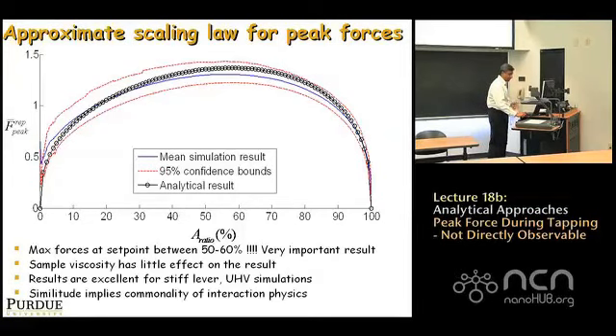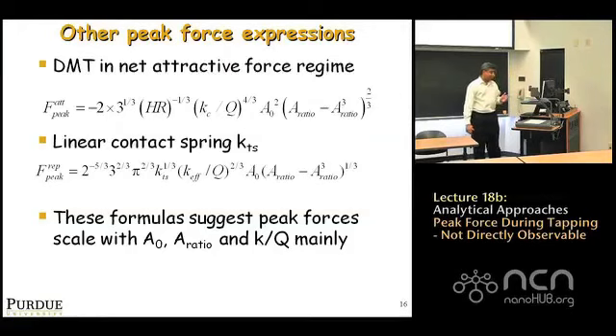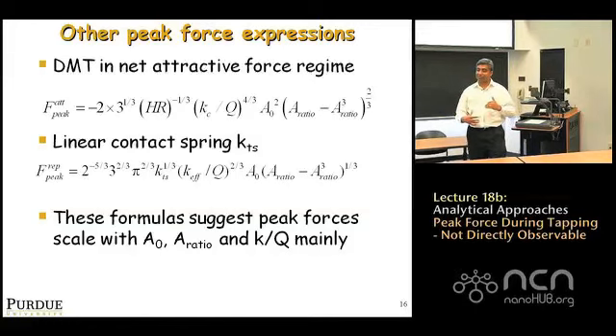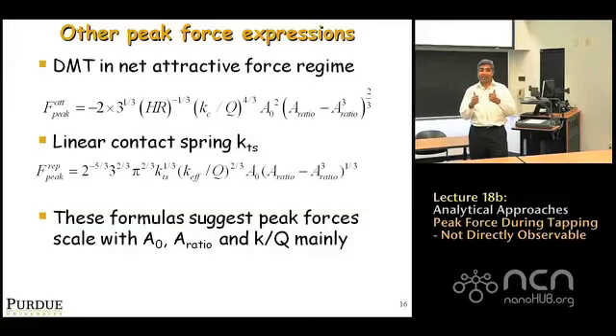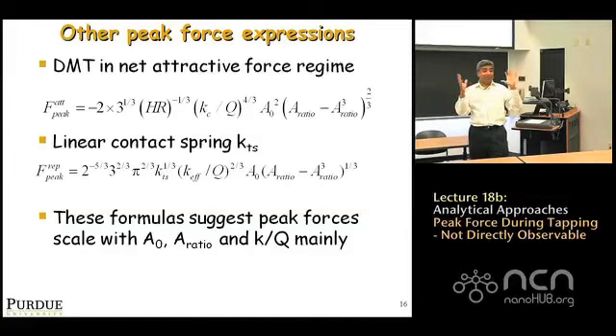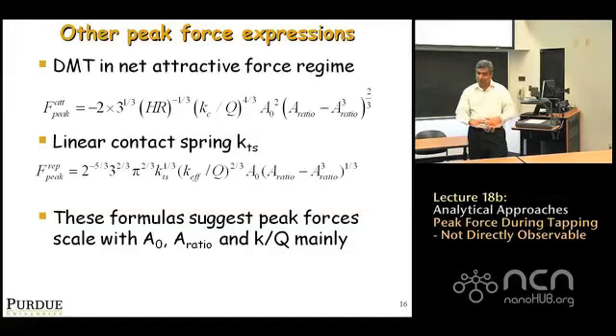The analytical theory allows closed-form solutions for peak forces for different interaction force models, giving a good idea of how interaction forces scale with local properties and what to do to reduce or increase them. Without this theory, you'd be optimizing over a vast parameter space — free amplitudes, set points, cantilevers, sample dependence — without knowing the key relationships. These expressions help focus on the important variables: low amplitudes and high or low set point ratios to reduce imaging forces.